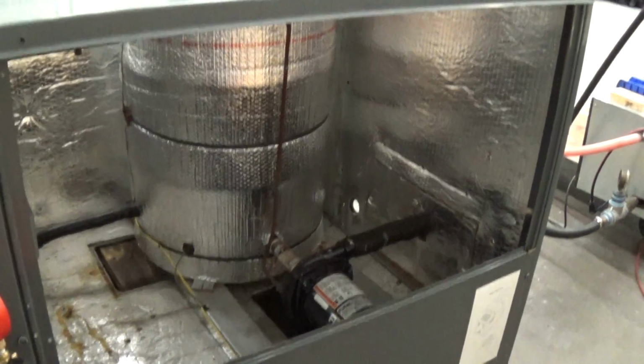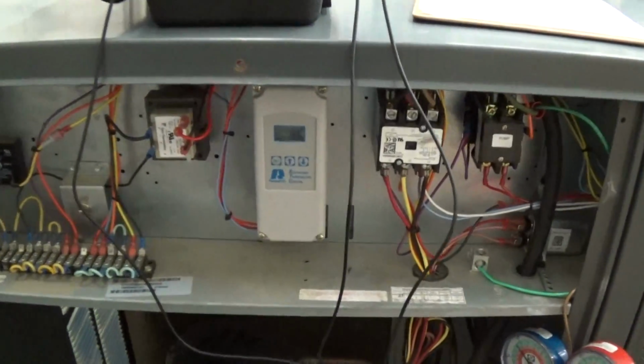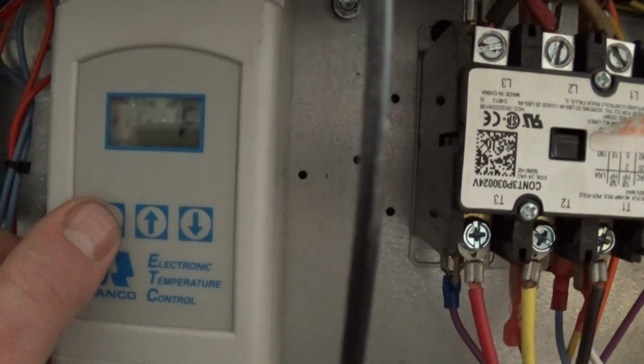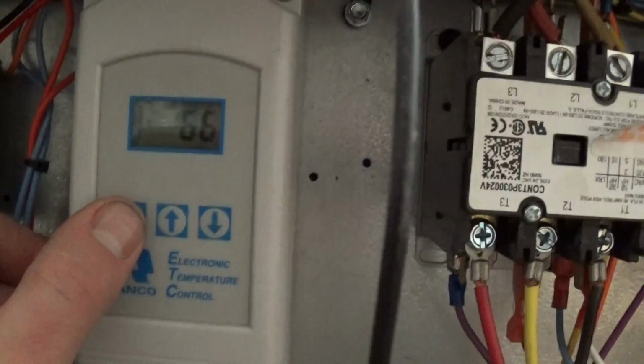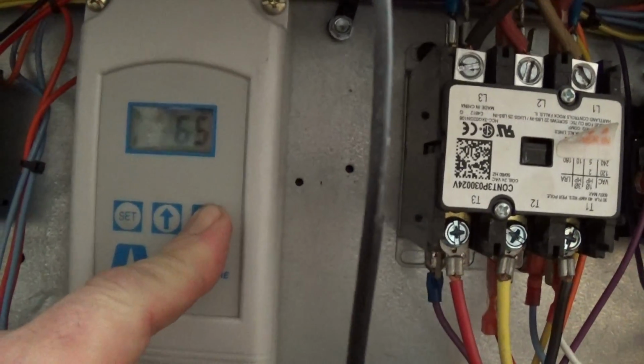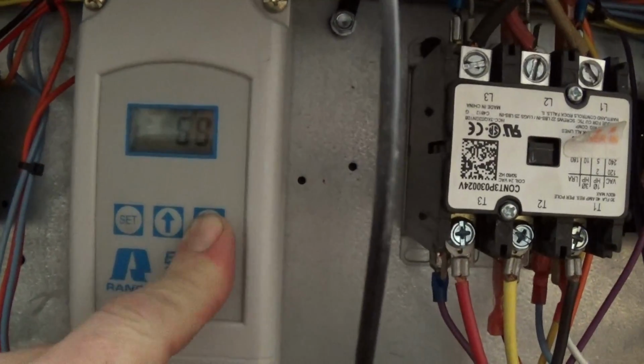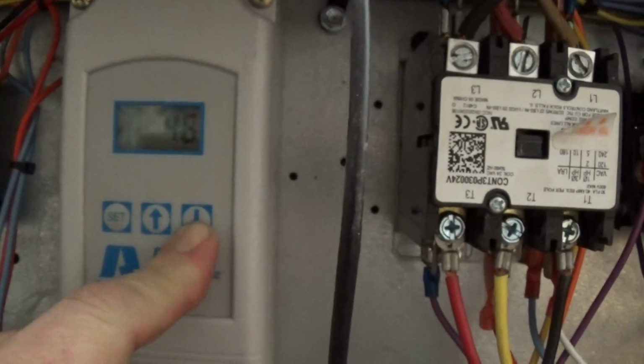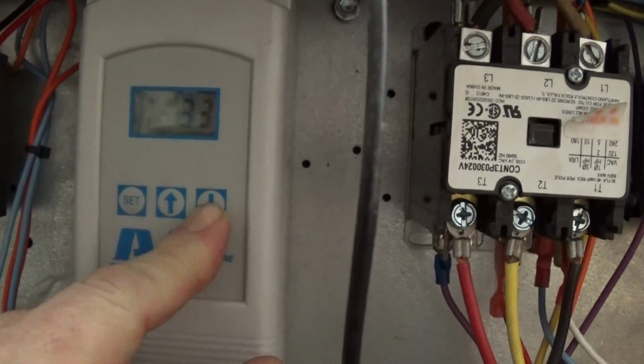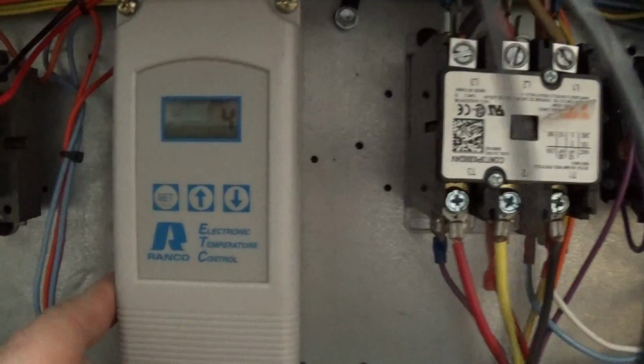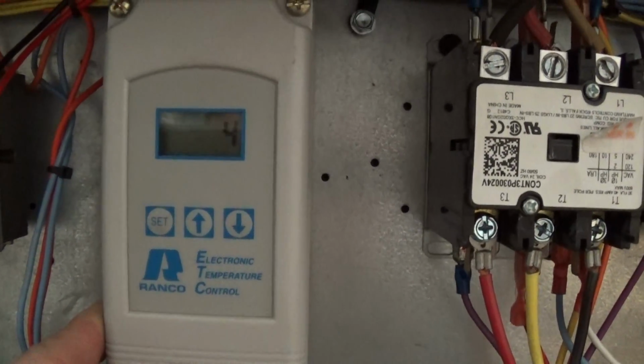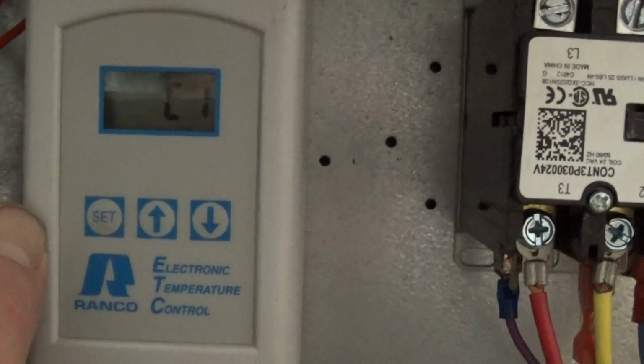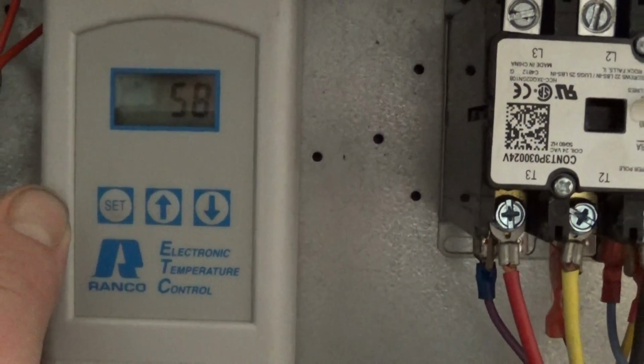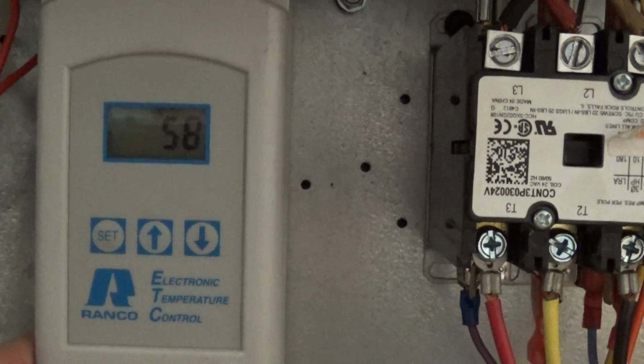For this application, the customer is going to chill to about 30 degrees fluid, glycol fluid temperature. So all we're going to do here is press set. That's for Fahrenheit. Keep it there. And then we have a set point at 65, so we're going to lower it to 30. And press set again. It'll show the next function, which is the differential of 4. We're going to leave that up there. C1, cooling mode 1. And then we're going to go back to what the process value is. So the fluid value is at 58 right now.